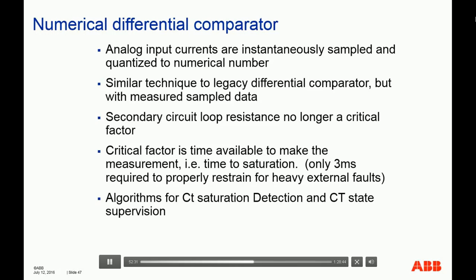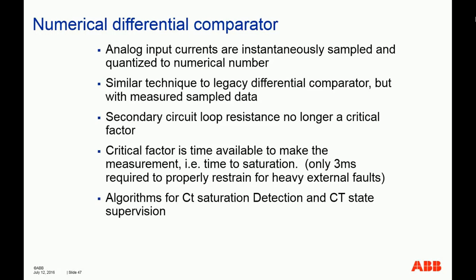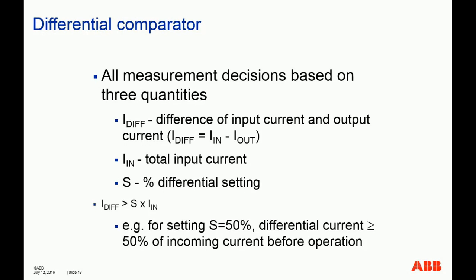Secondary circuit loop resistance is no longer a critical factor. The critical factor is the time available to make the measurement, also known as time to saturation. For example, in an ABB relay, only 3 milliseconds is required to properly restrain for a heavy external fault that causes heavy CT saturation. More or less, every vendor has the same type of CT saturation detector to help stabilize for heavy external faults.